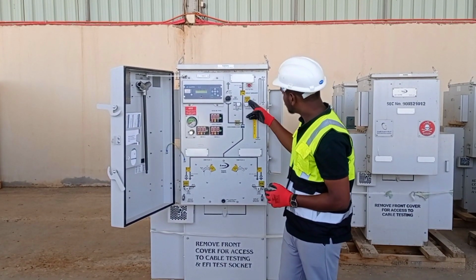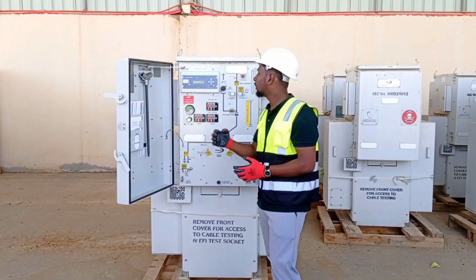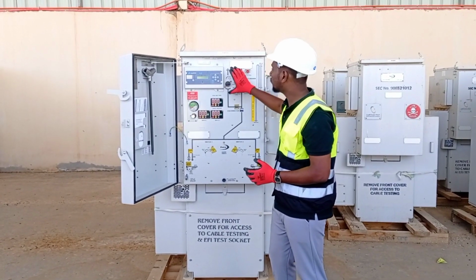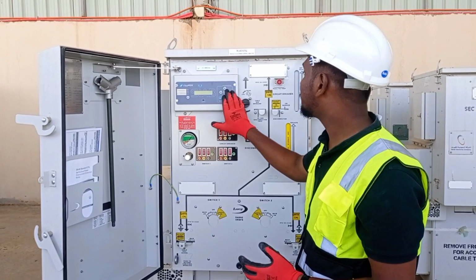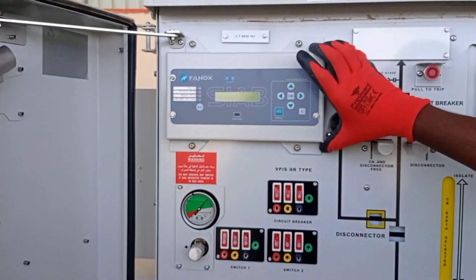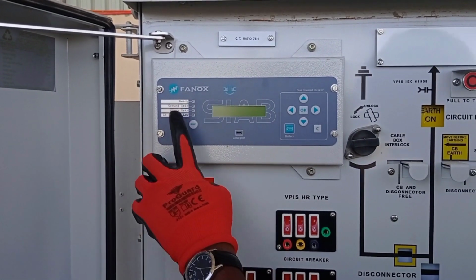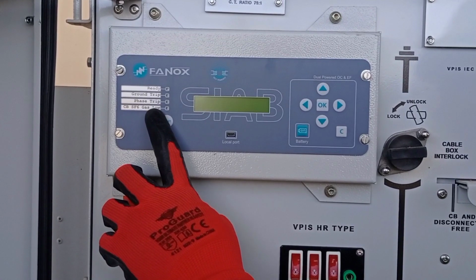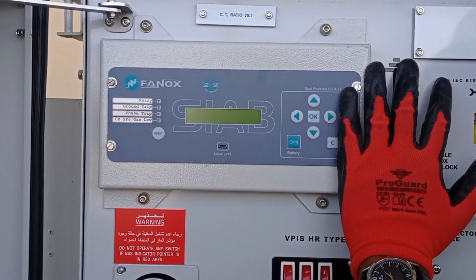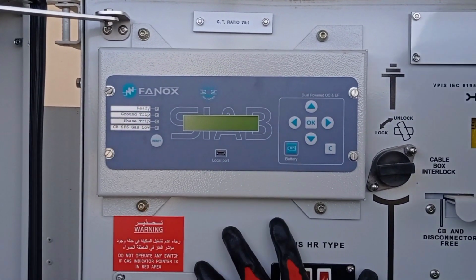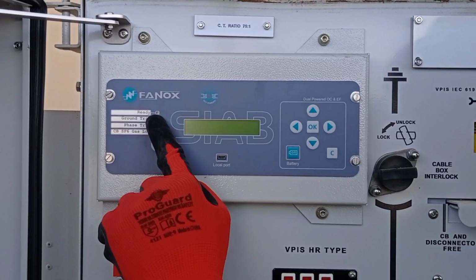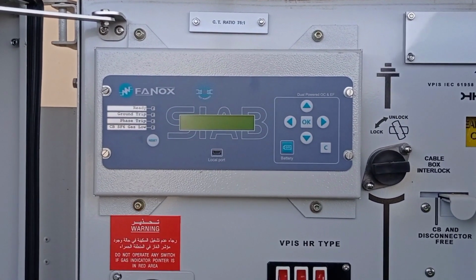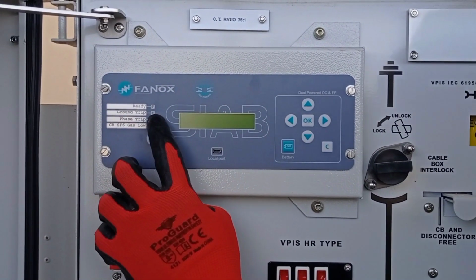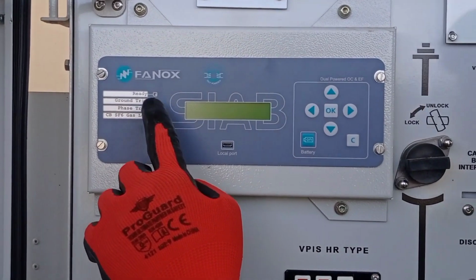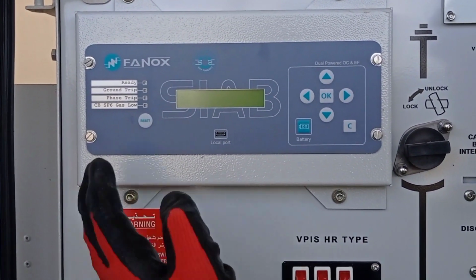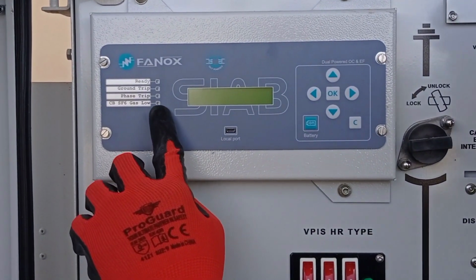There are also indications here. One of the important things in the RMU is this relay. Its name is the OCEF relay, the overcurrent earth fault indication relay. We can see many indications: ground trip, phase trip, CB, SF6 gas low. Once the RMU is energized, if the RMU condition is 100% ready, it will be indicated here as a green light. If any fault happens, a ground trip will be indicated here. If any phase trip happens, it will be indicated here. And if the SF6 gas becomes low, it will also be indicated here as red.